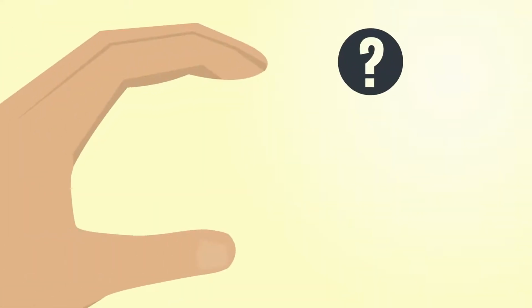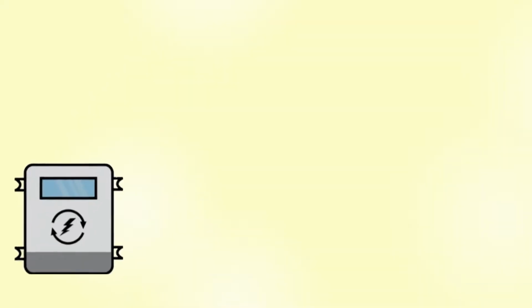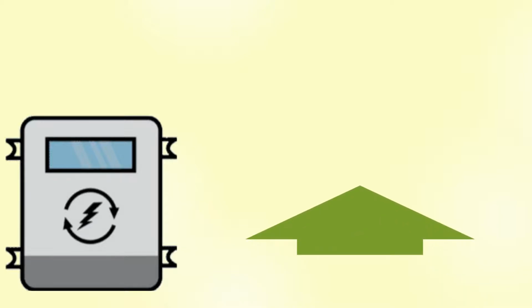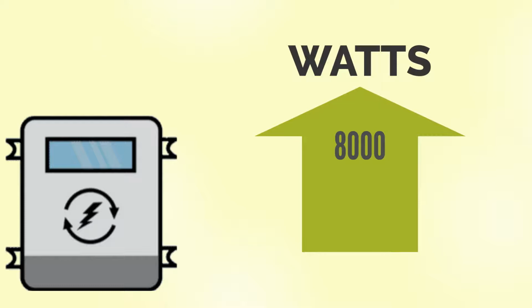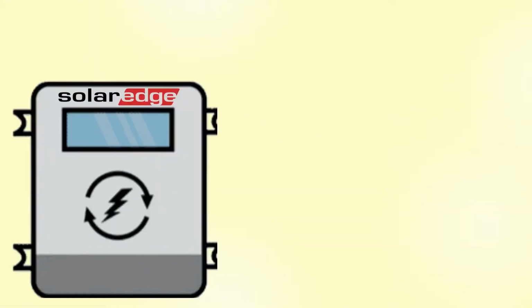You'll also receive questions about sizing a solar inverter. Solar inverters can be upsized by the manufacturer's instructions. This means an inverter that is 6,000 watts can actually handle a load of more than 6,000 watts. Upsizing a system allows solar companies to save more money when purchasing products, as the inverter can handle more solar panels than originally listed. For example, a typical SolarEdge inverter can be upsized by 155%.